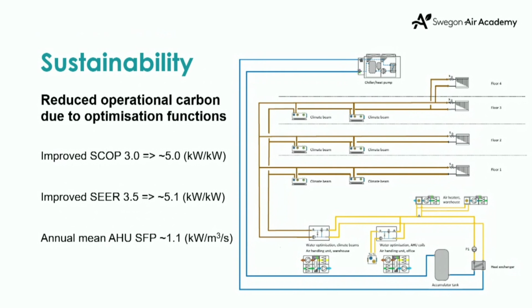And we are optimizing both the air side with the duct pressure and the water side with the water temperatures. So at plant levels, we monitor all the valve positions for all the cooling and heating coils. And we adjust the water temperature to keep at least one valve as open as possible. And when all the valves are closing, we send a new set value to the reversible heat pump.